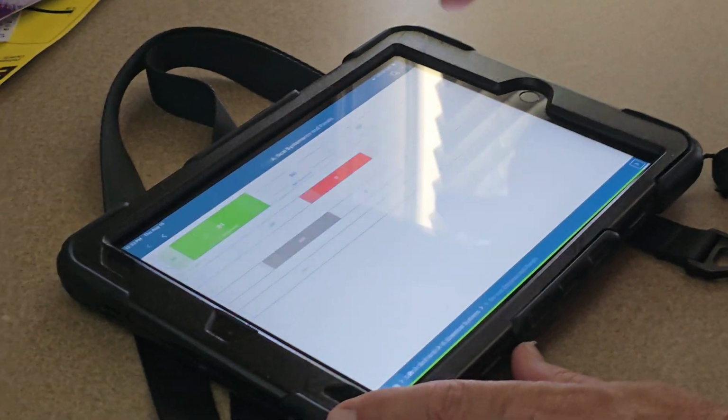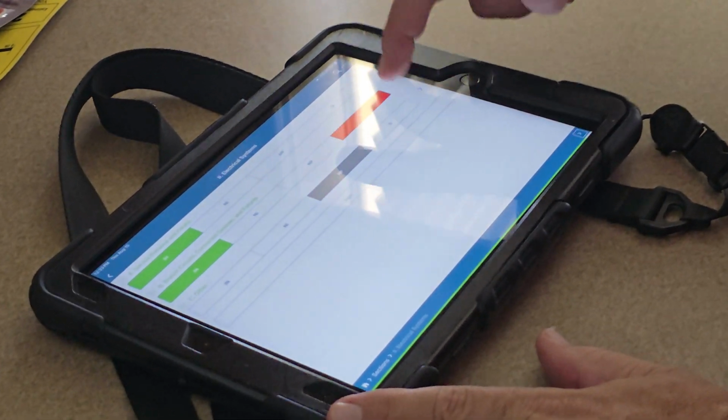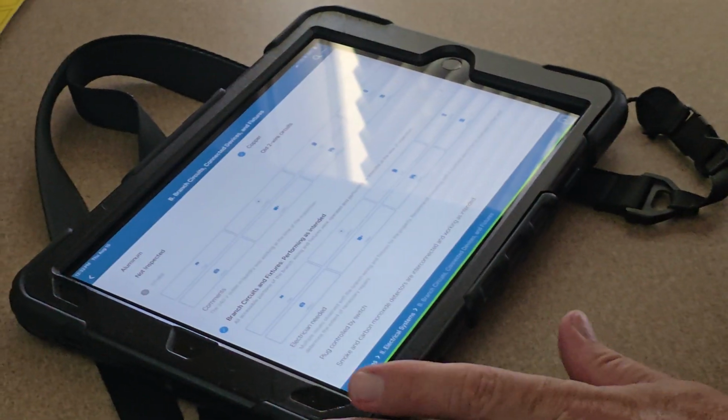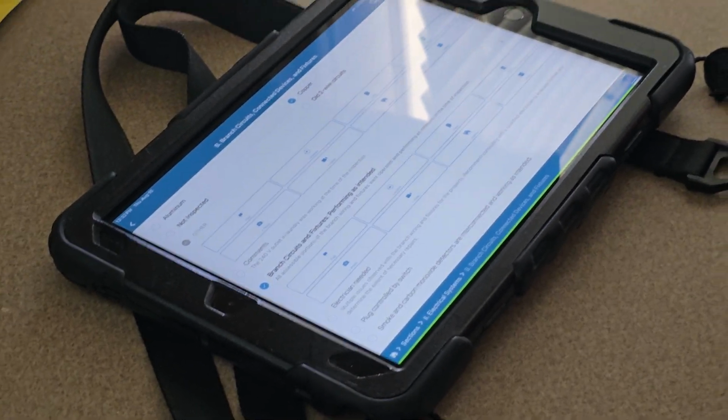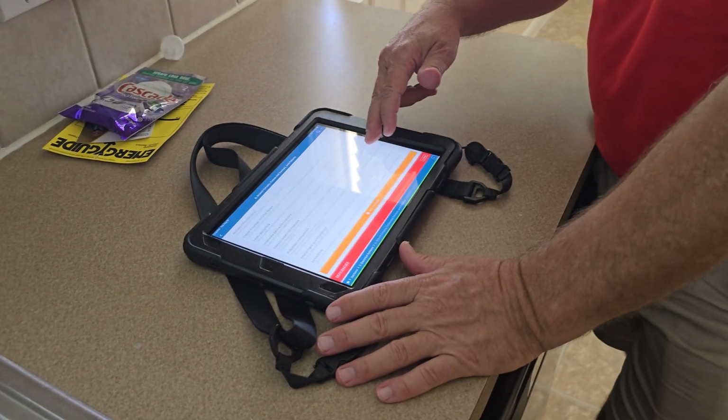everything looks pretty good in the panel. Not any issues in the panel. You've got aluminum bringing in the service and then copper distributing it throughout the house. That's typical for any home. And then on your, I'm sorry? No, I said I think that's correct. Yeah, on your branch circuits, which are switches, plugs, fixtures, and that type of thing.